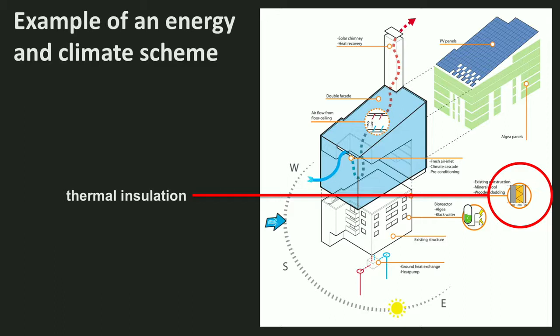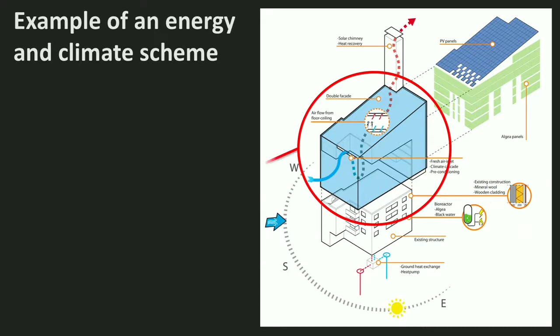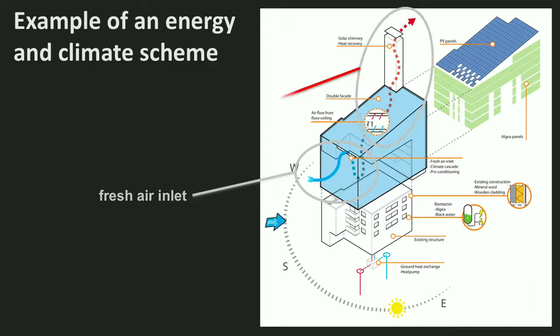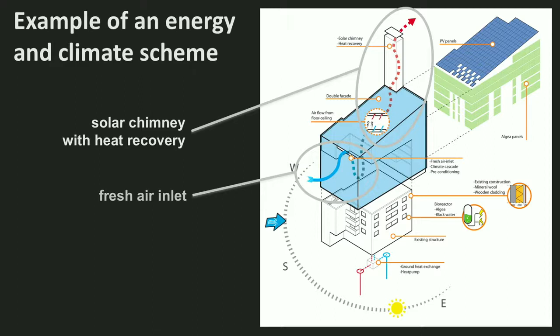He also added a double facade — a layer of glass over the existing building. Fresh air is let in through this double skin, passes through the building floor to ceiling, and leaves the building through a solar chimney. At the top of the chimney, heat is recovered from the air — you can only do that at the top, because otherwise the thermal draft will not work. The heat extracted is then stored in an aquifer thermal energy storage underground, and in wintertime this heat will be used to heat the building.